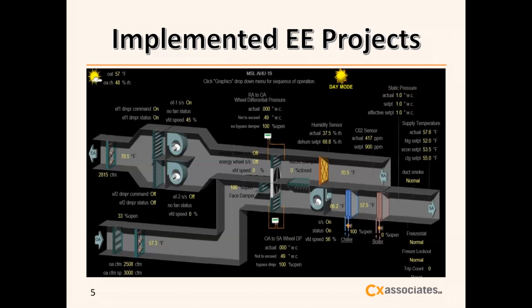There are also many small control sequence changes to the boilers, the chiller plant, the pumps, and the fans, which optimize temperature and pressure set points according to the outside air temperature or interaction with downstream components. Altogether, these tweaks added up to the considerable energy savings we saw in the 2030 district energy analysis.